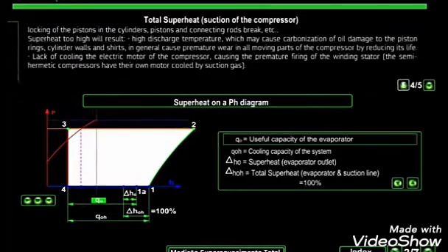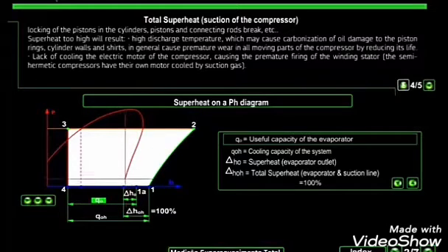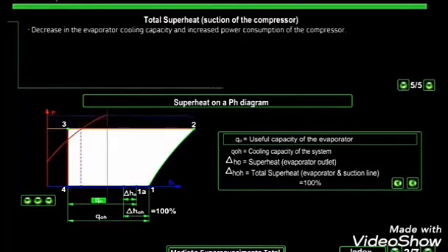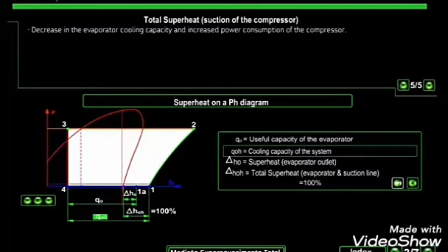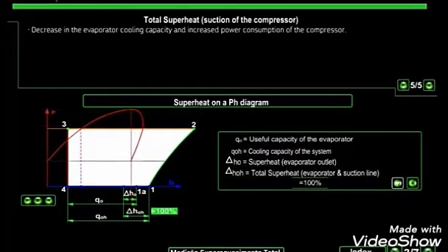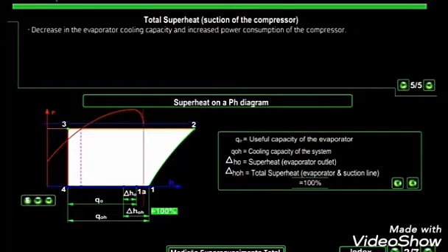The expansion valve superheat setting. The thermostatic expansion valve superheat setting leaving the factory is approximately 6 Kelvin. Its adjustment may be necessary. Step 1, after starting the compressor, let the plant settle to its running conditions. Second one, remove the cap, rotate the adjusting screw, and wait for the cooling system to come into balance again.